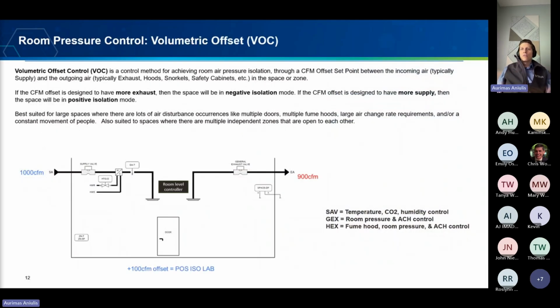When we look at volumetric offset controls, we have a basic kind of a setup here with a supply valve, reheat coil, duct temperature sensor, and we have a general exhaust air valve that is controlling for 900 CFM exhaust and 1,000 CFM supply. Now, supply will typically modulate for temperature because the reheat coil's on the supply side. The general exhaust, in this case, will modulate for pressure and air changes per hour. In this specific application, we have 100 CFM positive offset. This means it's a positive isolation room. If you're a burn victim, infection is a problem, so they'll put you in a positive isolation room.